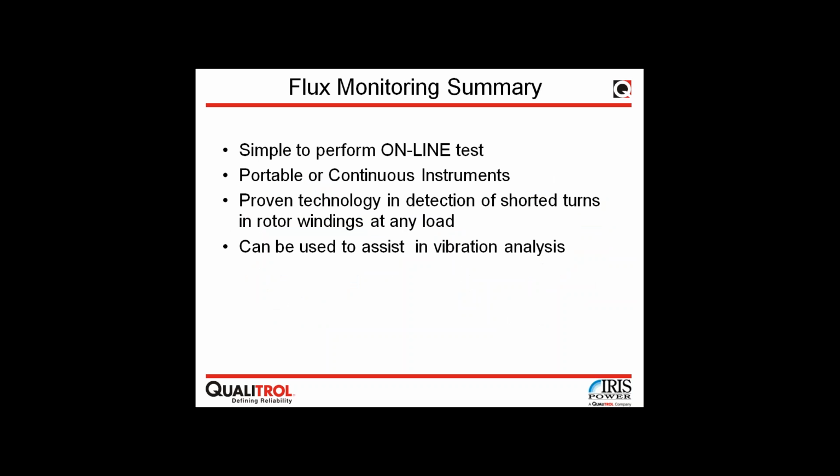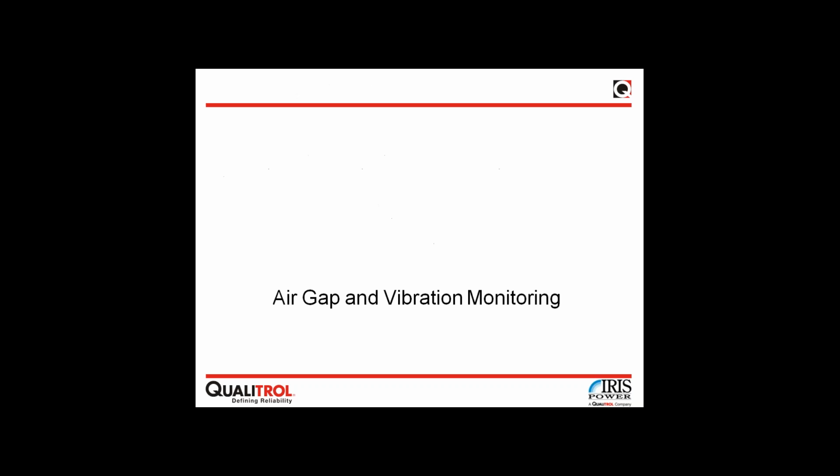People are generally not worried about shorted turns or shorted poles as long as they can operate normally, but in a case of a higher vibration level, it is necessary to troubleshoot where that level is coming from, or what the cause is. So flux monitoring is one of the methods assisting the operator to find out if the problem generated by the machine, resulting in mechanical vibration, is mechanical or electrical in nature.